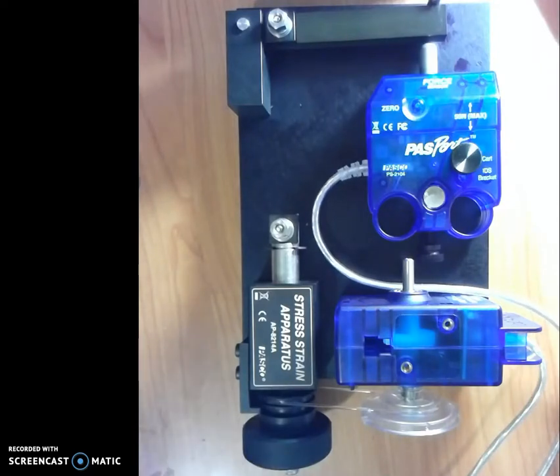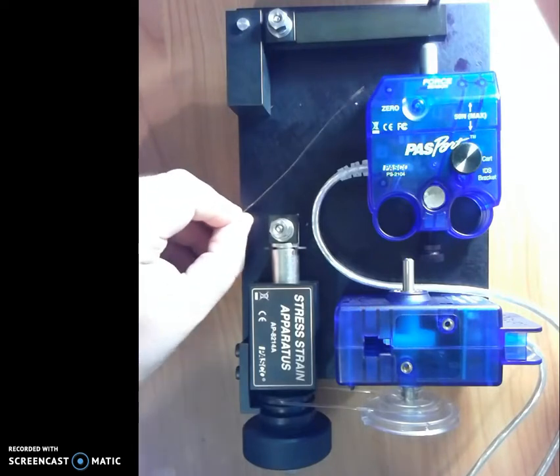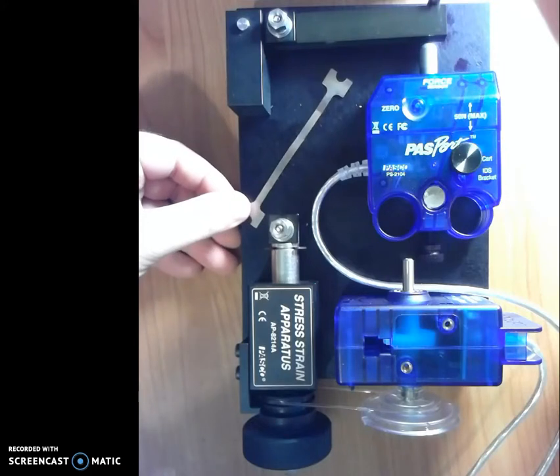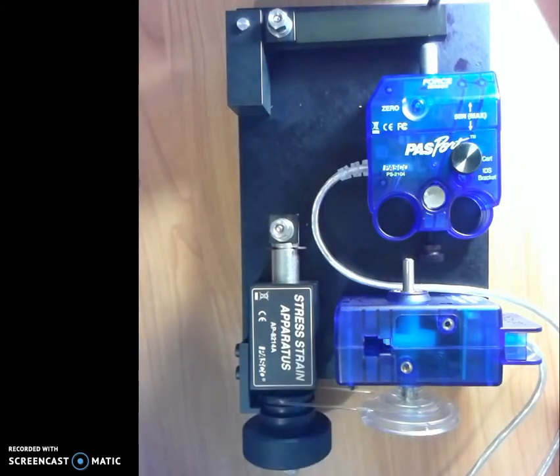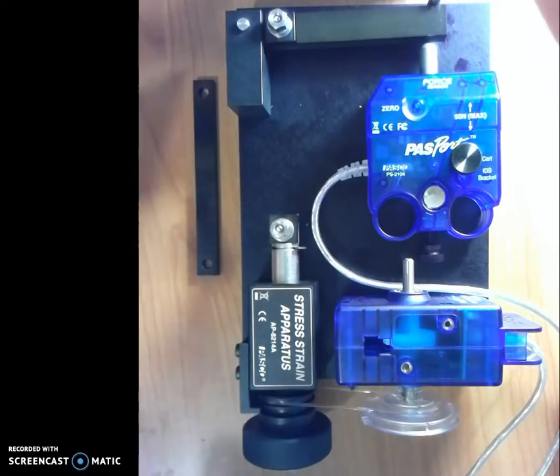Now, the first thing that we have to do is calibrate this thing. The reason we have to calibrate it is even though the sample coupons themselves, here's one for example, are quite small. You can see if I turn this on its side, it's just as thick almost as a piece of foil, but anyway, they're quite small. So even though most of the force and displacement is concentrated onto the coupon, there is still going to be some bending in the apparatus, and we need to figure out what that bending is and subtract it away to get a correct stress strain curve for the sample coupons. And so the way that we do that is we introduce a very rigid component, which is this guy, called the calibration beam. The calibration beam is going to sit in here, and we're going to just calibrate how much the whole system deforms when the calibration beam is in place, and then use that information again to subtract away to determine the remaining force and displacement on the samples when we get that far.